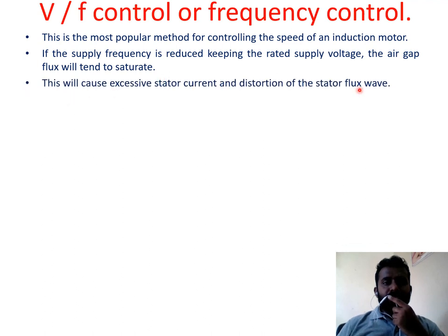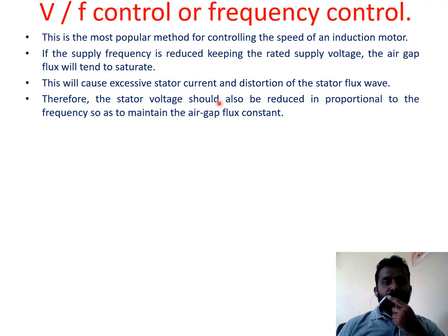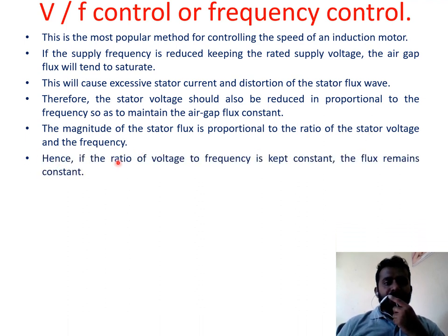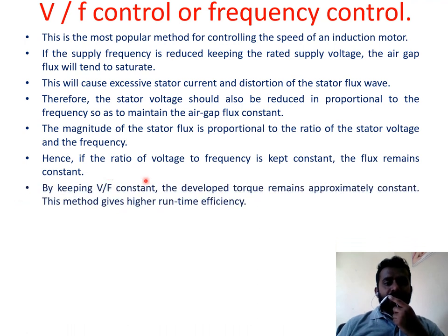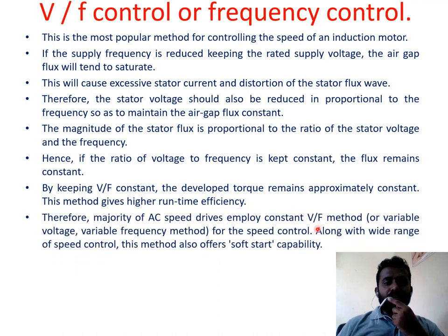V/F control or frequency control is the most popular method of controlling the speed of an induction motor. If the supply frequency is reduced while keeping the rated voltage, the air gap flux will tend to saturate, causing excessive stator current. Therefore, stator voltage should be reduced proportionally to the frequency to maintain constant air gap flux. By keeping V/F constant, torque remains approximately constant and higher run-time efficiency is achieved. This method also offers a soft start capability.